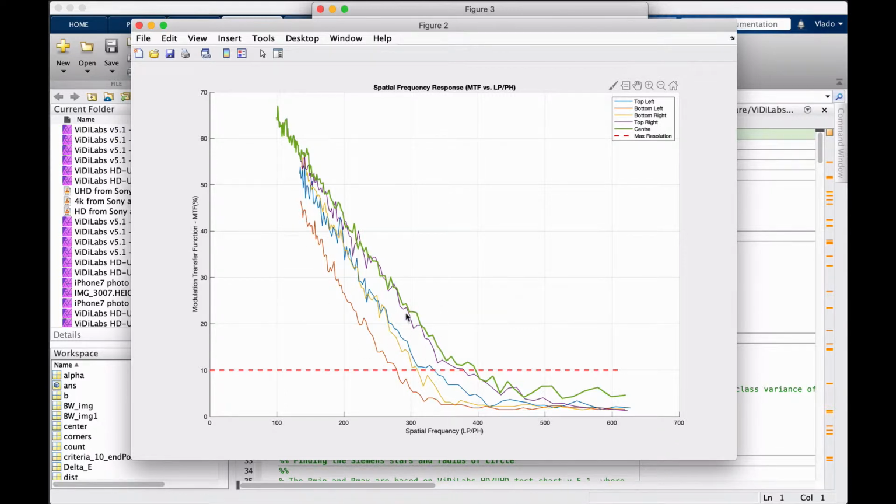Sometimes based on these differences you can judge the perpendicularity of the sensor relative to the optical axis. In fact, we have found in our many experiments and tests in the past, some camera manufacturers don't have perfect alignment of the sensor relative to the optical axis. If your setup alignment is proper, when you measure the test chart, you may notice that particular camera models have either the left-hand side or the right-hand side sensors completely out of focus relative to the center one, which may indicate that sensor alignment is an issue.